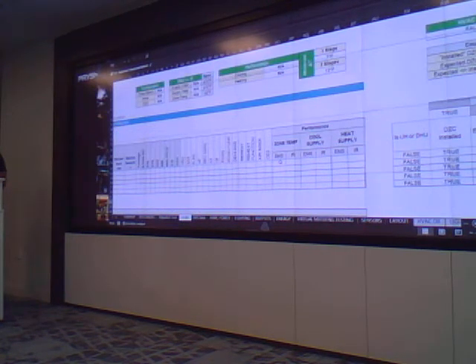There's also performance testing over here, where you're looking at either direct connecting to the system itself, or usually what's going to be easiest is just looking at the portal at this site, forcing that unit into cool, seeing the difference between what you see online on the portal versus your handheld. There's already logic put into here that's saying a couple of degrees is okay. And then what you'll also see, we'll put in just some numbers here. Say...